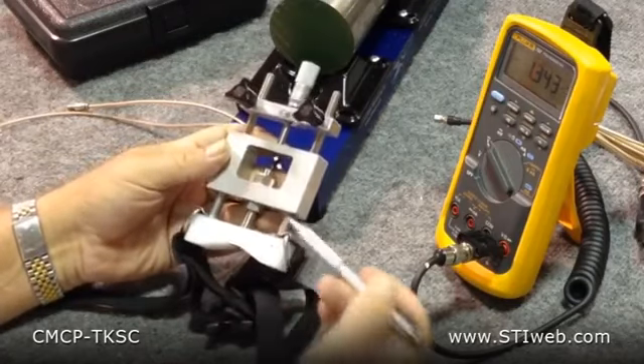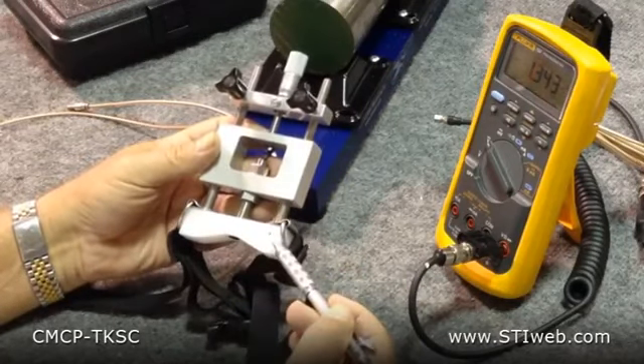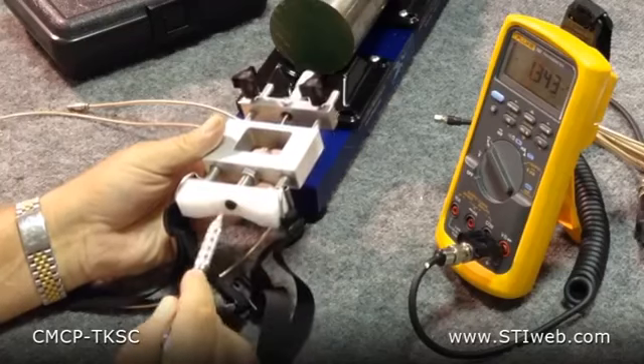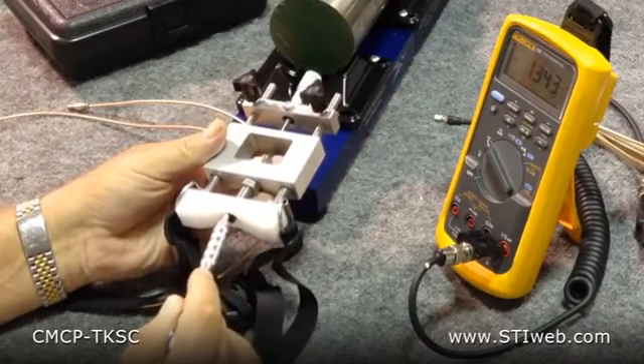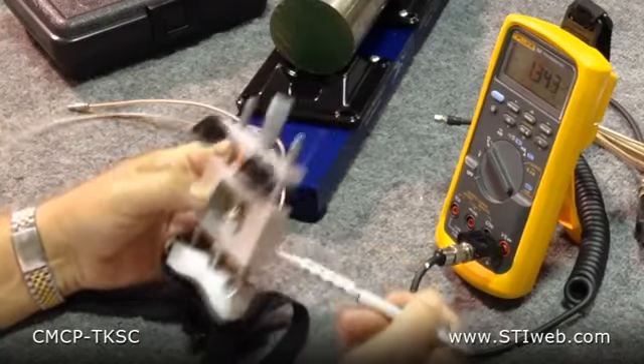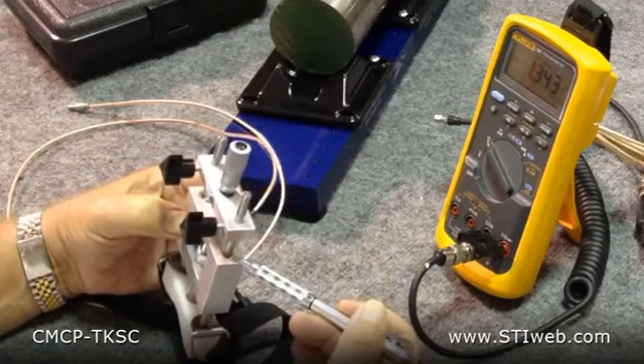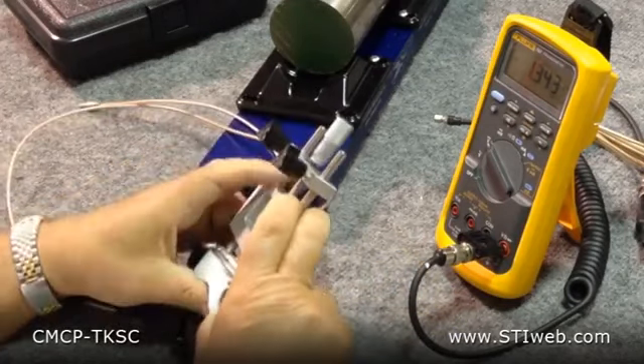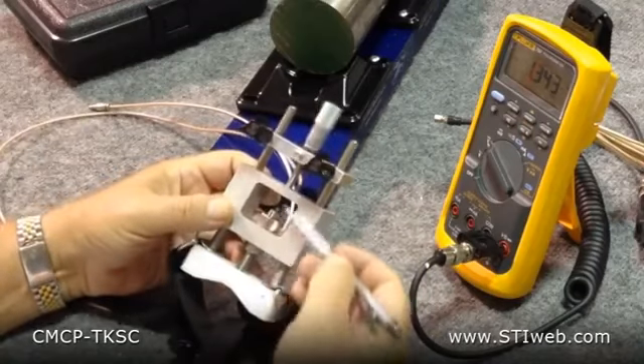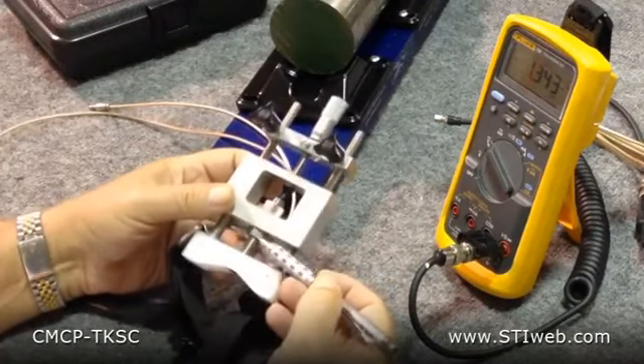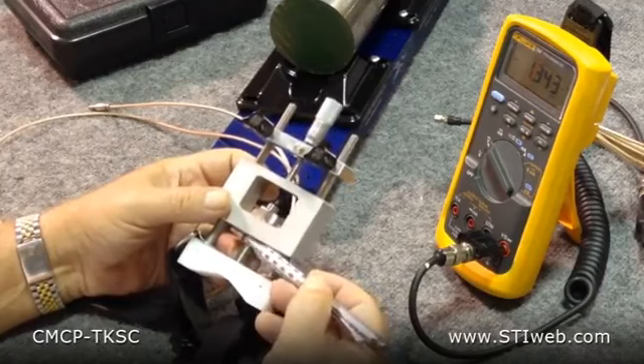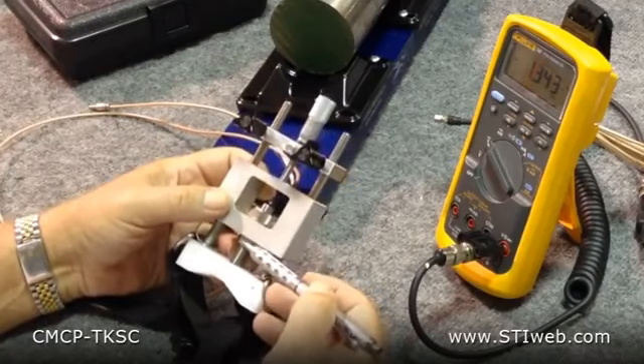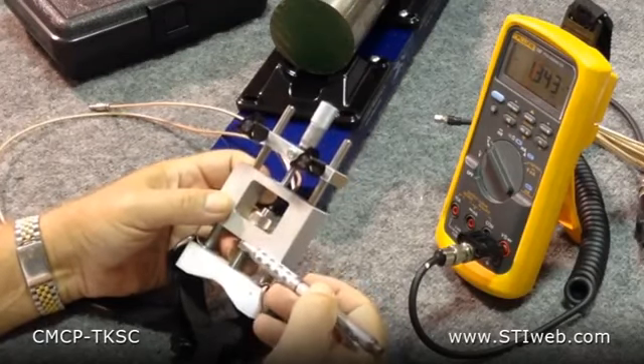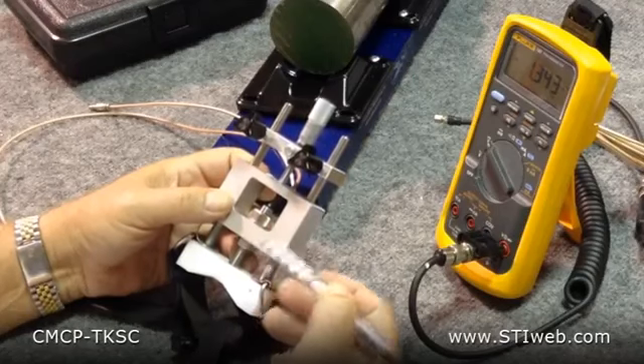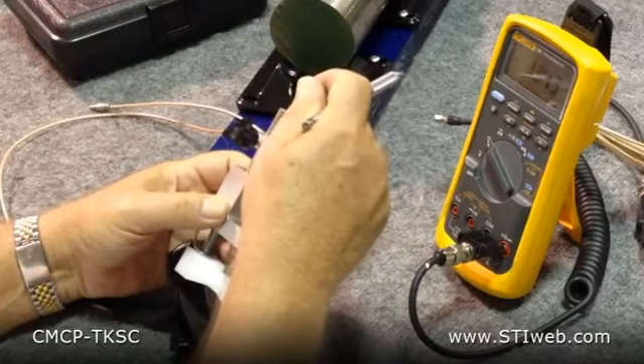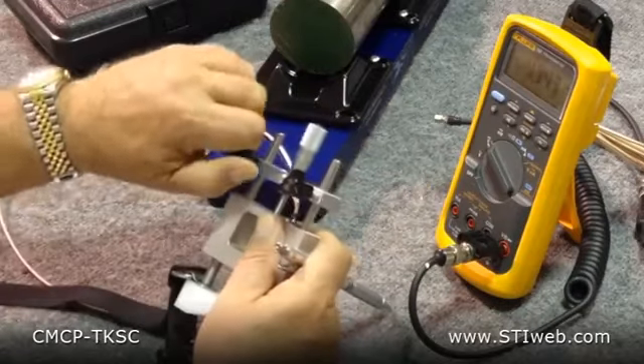It's made up of a couple parts. It's got a base plate made of nylon, so it does not affect the RF field from the proximity probe. It's made up of an armature that has bronze oil bearings in it to make it slide up and down the shaft very, very easy. The armature holds the proximity probe by using 2 nuts. You can take a 1/4 or 3/8 inch proximity probe or any of the metric sizes up to 0.400 in diameter. Then you have a top plate that holds the dial micrometer, and the top plate can be adjusted.